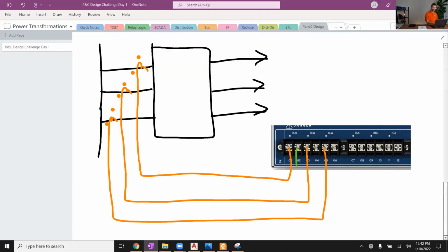Green is a common color for neutral. See, this is like a jumper. And then likewise over here in the breaker CT terminal blocks, we would tie those together and jumper them. And then we got to tie those 2 ends together from the breaker bushing CTs to the relay CT terminals. So we're going to bring that neutral over here.